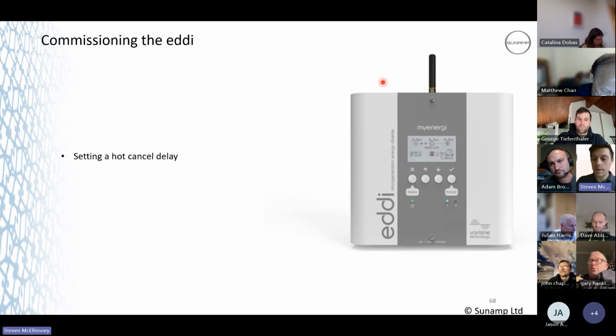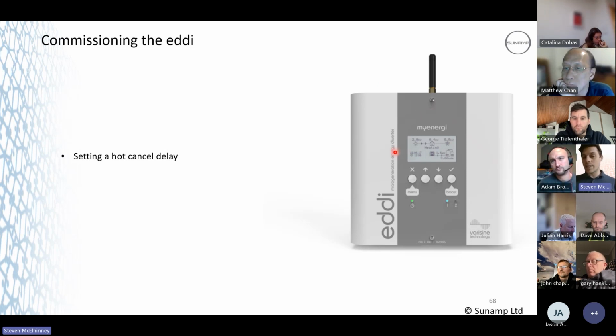What the eddi does, as I was saying, we've got a soft overheat. When the sensor detects that the battery's too hot at the base of it, it cycles off the element and allows it to cool, and then it'll come back on again. The eddi recognises the flow of electricity, whether something's reached temperature or not. So on its off cycle, the eddi will recognise no flow of electricity, maximum temperature reached, but it's not the case. What the hot cancel delay does is tell the eddi to ignore that message for whatever time you set.